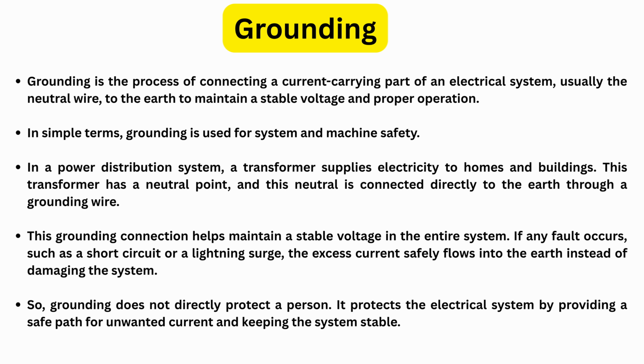The earth is our electrical sea level, it's the absolute zero. By grounding the neutral wire at the transformer, we lock it to 0 volts. This keeps the entire system stable. Without this connection, voltage can become unstable and equipment may not work properly.